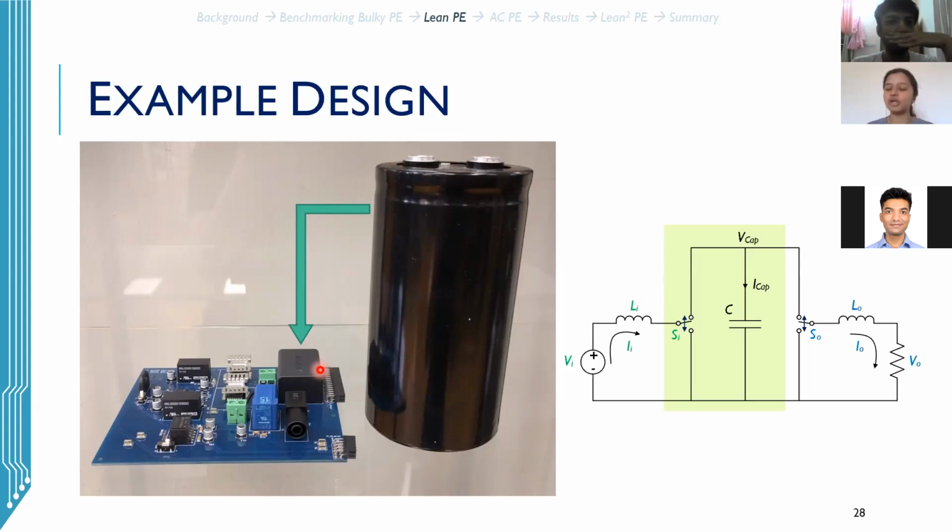And now, in addition, there is some work going on wherein we look at active capacitor cooling schemes. So moving towards high density power conversion, in many applications, we cool the switching devices, but we do not always cool the capacitor, because we're using a big capacitor which has a bigger footprint, and the natural convection or natural cooling is enough for it.